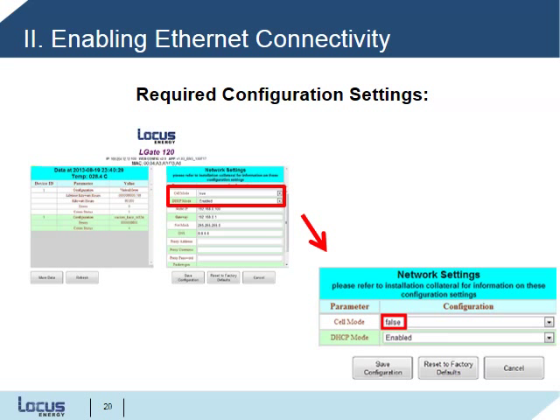The one thing that we need to change is the cell mode. We'll change this from false to true. Then select the Save Configuration button. After making this change, the LGate Ethernet connection will now be enabled. Keep in mind that the LGate cannot automatically switch between an Ethernet connection and a cellular connection. So anytime you need to adjust the connection method, you'll need to log in and manually change these settings.